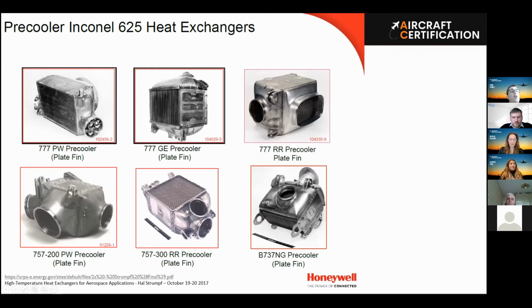And another issue with precoolers is the stratification of bleed temperature. If you have a temperature sensor here in the outlet of the precooler, because of the nature of this component to have distributed temperature parameters inside, probably you have stratification in the outlet. And in this picture here, it clearly shows a mixer. So here you have fins whose intent is to mix the stratification that's generated inside the heat exchanger, and to mix the streams to make it easy to control the temperature, because you have a temperature sensor here that will control the fan air valve. And if you have a wrong reading of temperature, you will not be able to control the temperature. So this is another hydraulic element that contributes to avoid stratification in the outlet.